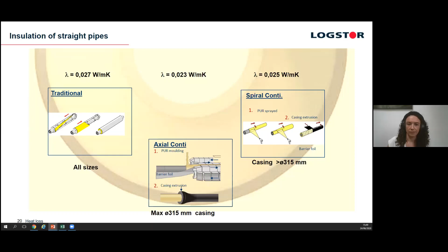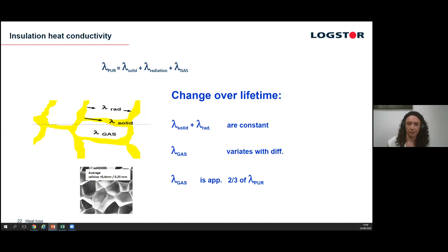The big effect really of that diffusion barrier is to prevent aging. So what we have in our foam, it's not the foam that's actually providing the insulation. All the foam is doing is simply a carrier to put some closed cells in there, and those closed cells have gases in them. So we've got some really good gases in there, which are really high insulating gases. So cyclopentane, we've got 0.012 lambda value, and we've got CO2, which is 0.017.